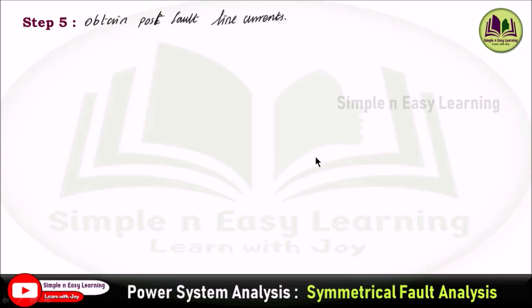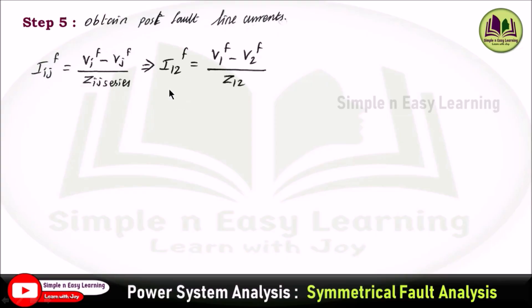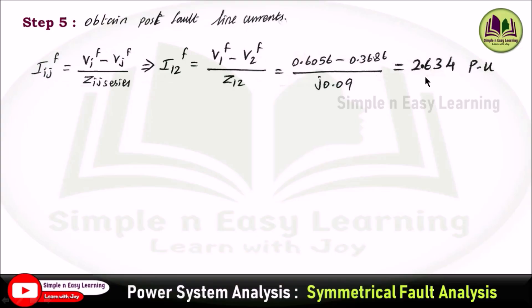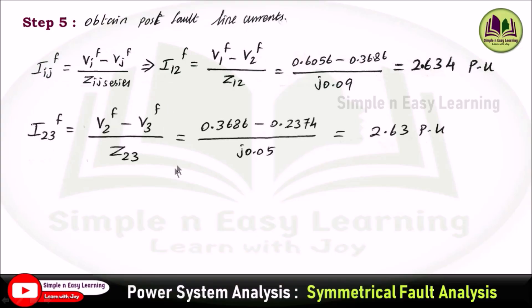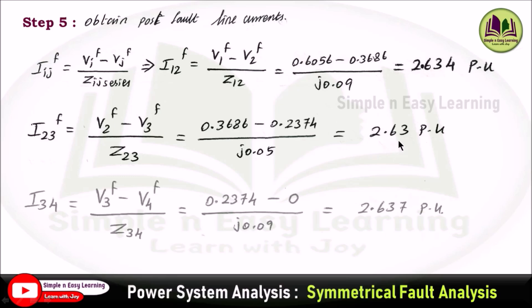Step 5: obtain post-fault line currents using I_ij = (V_i − V_j) / Z_ij(series). For I12: substituting post-fault voltages and series impedance gives 2.634 per unit. Similarly, I23 = 2.63 per unit and I34 = 2.637 per unit. This completes the symmetrical fault analysis using the bus impedance matrix method.